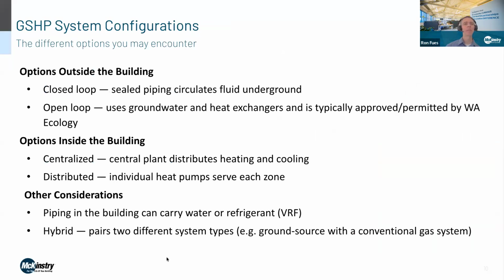Okay, next slide. Okay, so we could probably have 10 slides on different options with ground source heat pumps. HVAC is very complex, but just to break it down to the really high level, outside the building, you can have open loop or closed loop. So those are the two big categories, and that's the big decision. So closed loop is more common, and that's where you have that plastic piping, and you might have hundreds of loops of plastic piping going down a couple hundred feet, circulating water in closed loop plastic piping. And then open loop is a little bit less common, but it's becoming more common and, if your site is right, can have a lot of cost savings. So it can be cheaper to do open loop than closed loop. So that's one reason to consider that.